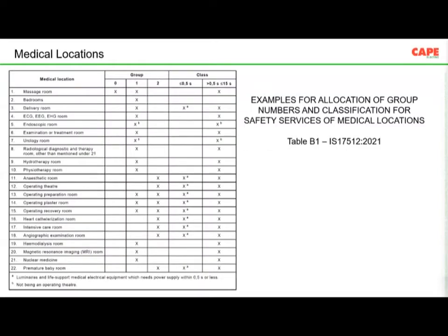But when it comes to the electrical installation, I am showing you the table B1 of IS 17512/2021, examples for allocation of group numbers and classification for safety services in medical location. So here on the left side, you can see some typical examples. For example, massage rooms, delivery rooms, how to categorize. Say, for example, anesthetic room, it is a group 2 location. Operation theater is a group 2 location. Then heart catheterization room is group 2 location.